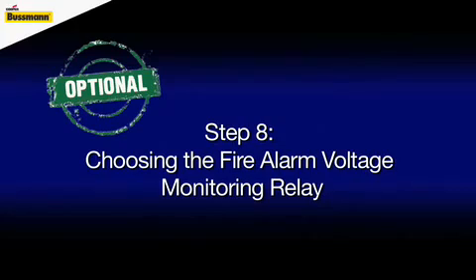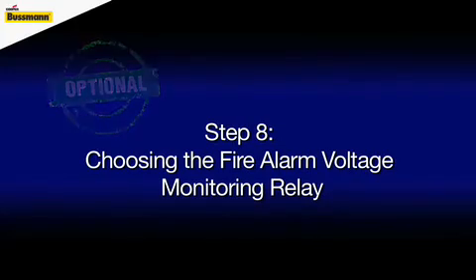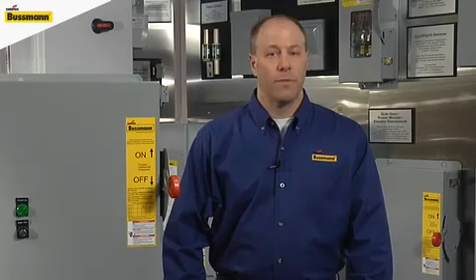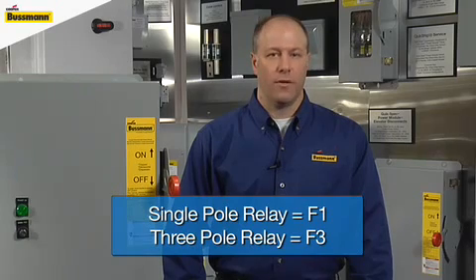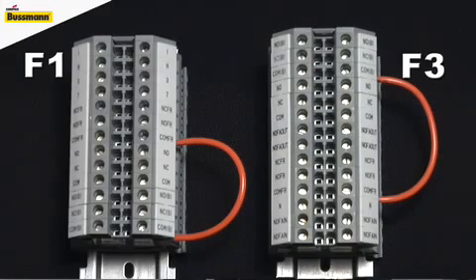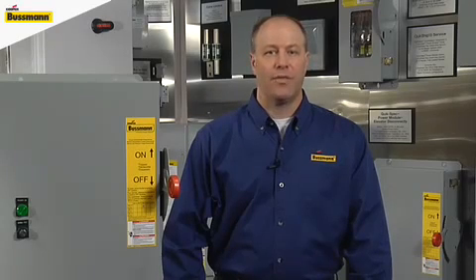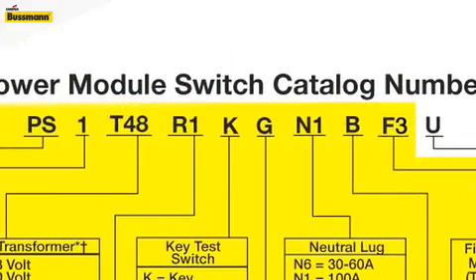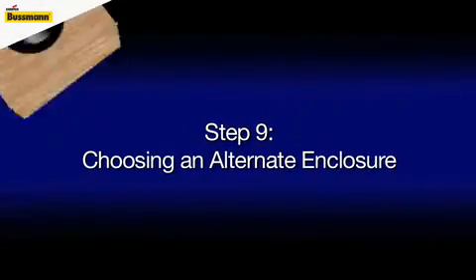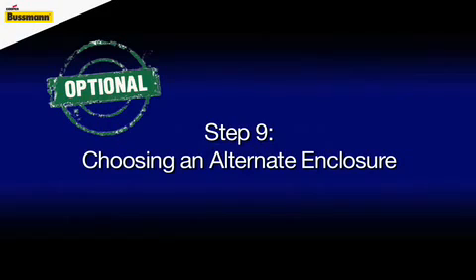Selecting the voltage monitoring relay component in step eight also depends upon your local code requirements. Cooper Bussmann offers two options: one is the single pole relay or the F1 option, and the other is the three pole relay or the F3 option. This provides the ability to meet code requirements for communication with the fire alarm control panel in all 50 states and Canada. Best of all, Cooper Bussmann offers either option at the same price. For our example, we will add the F3 code to our part number sequence.